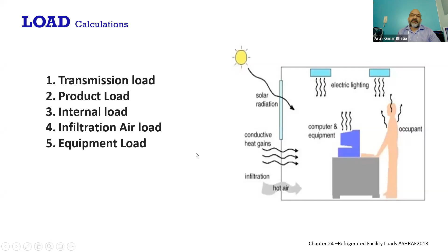If you see here, I have a room. The room is 10 meters length, 10 meters width, and 10 meters height, so the volume is around 1000 meter cube. So the load of the room, when we calculate based on transmission, product, infiltration, equipment, and the safety factor which we add to the load, this can vary from 10 kilowatt to 55 kilowatt for sensible load.